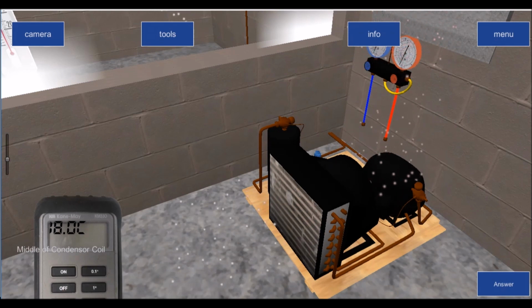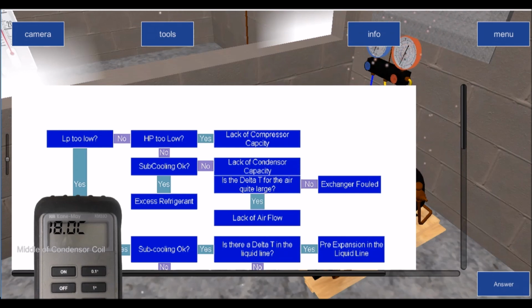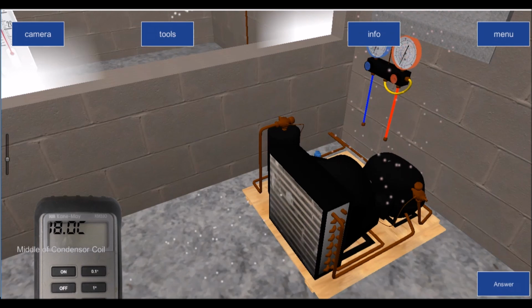Yeah, there, 18 degrees. Sorry, this was compressor pumping. In this particular case, yes, you can have the 18 degree condensing temperature, because what's happening is, if we go back to our chart, you've got your low pressure, low temperature vapor, which is going to be slightly higher, equalizing with your high pressure, high temperature vapor. So that's why you're getting your 18 degrees. So in other words, the lack of compressor means that we're not getting superheated vapor. So this here will be high pressure, high temperature, superheated vapor coming into the condenser, but because for whatever reason there's no compression actually taking place in here, effectively what you're getting is low pressure, low temperature vapor coming in here, equalizing with whatever the high side is, the high pressure. So it's bringing down the high pressure and it's bringing up the low pressure. There's no compression, no heat of compression taking place.